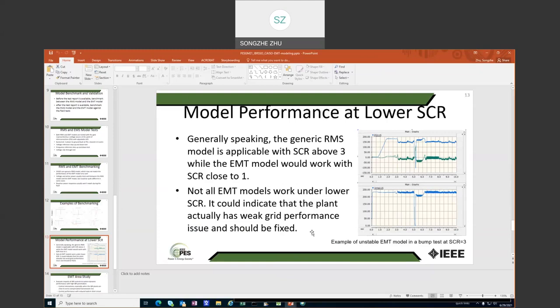But it could also be an indication that the plant actually has a weak grid performance issue and should be fixed. On the right, you see an example. At SCR equal to 3, you can see that the model isn't stable. When this happens, it needs a lot of debugging to check whether it is just a modeling issue or a real issue. And this typically involves help from the OEM since the model is a black box.